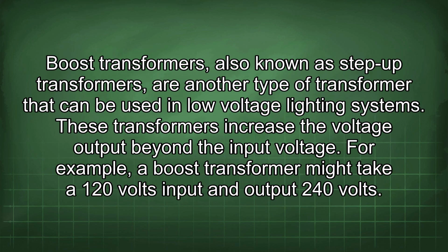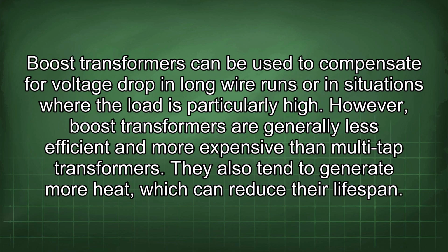Boost transformers, also known as step-up transformers, are another type of transformer that can be used in low-voltage lighting systems. These transformers increase the voltage output beyond the input voltage. For example, a boost transformer might take a 120 volts input and output 240 volts. Boost transformers can be used to compensate for voltage drop in long wire runs or in situations where the load is particularly high. However, boost transformers are generally less efficient and more expensive than multi-tap transformers. They also tend to generate more heat, which can reduce their lifespan.